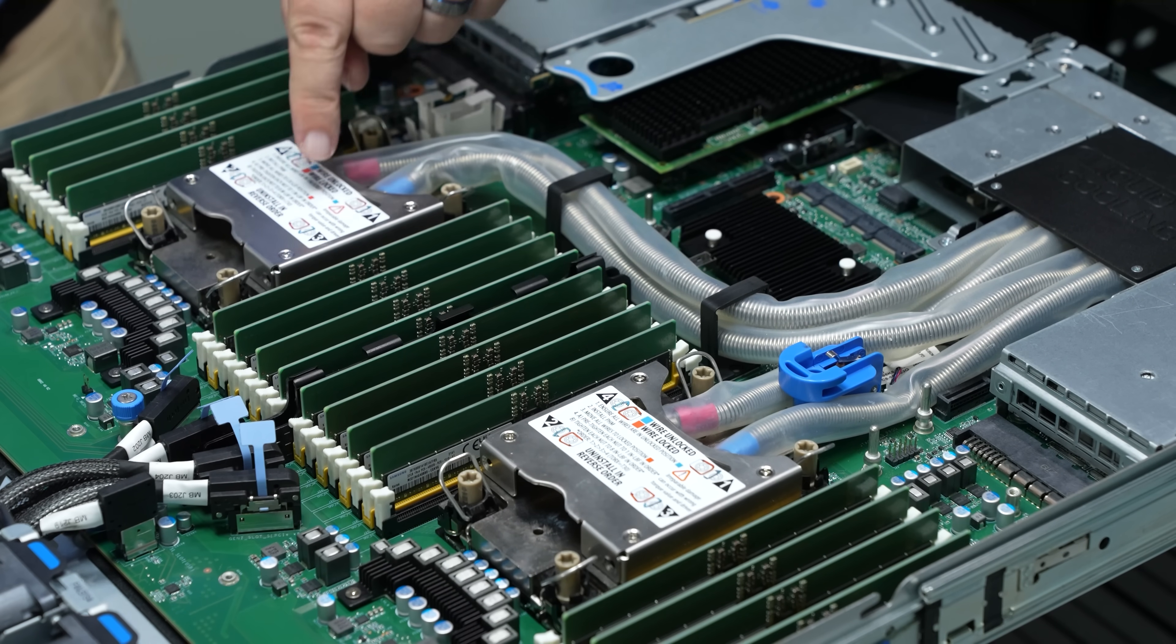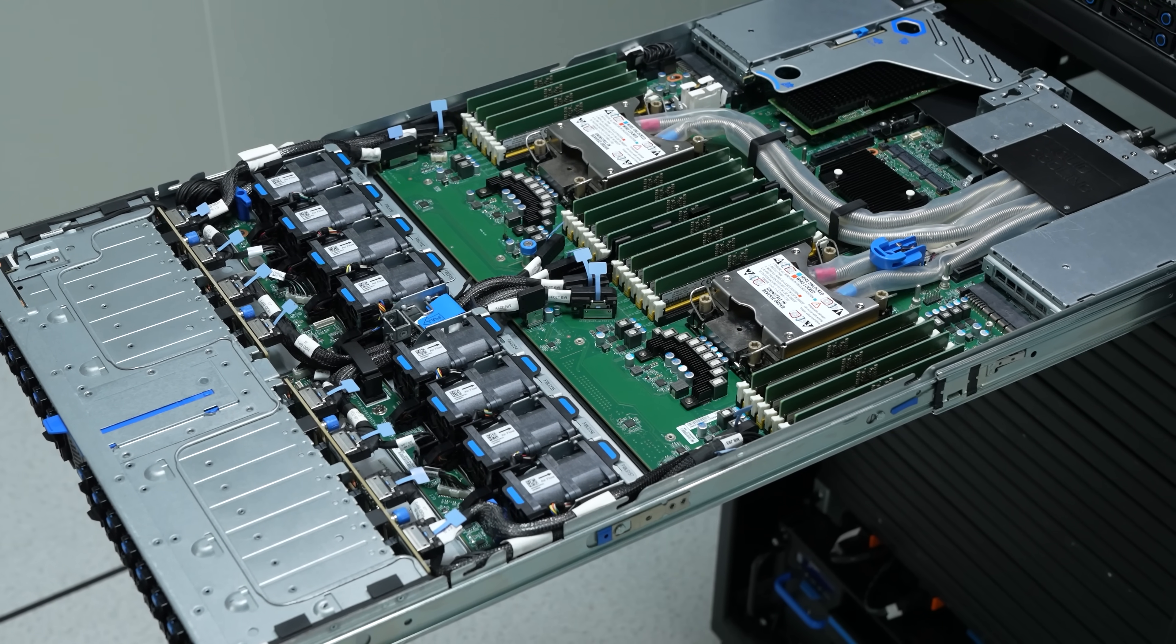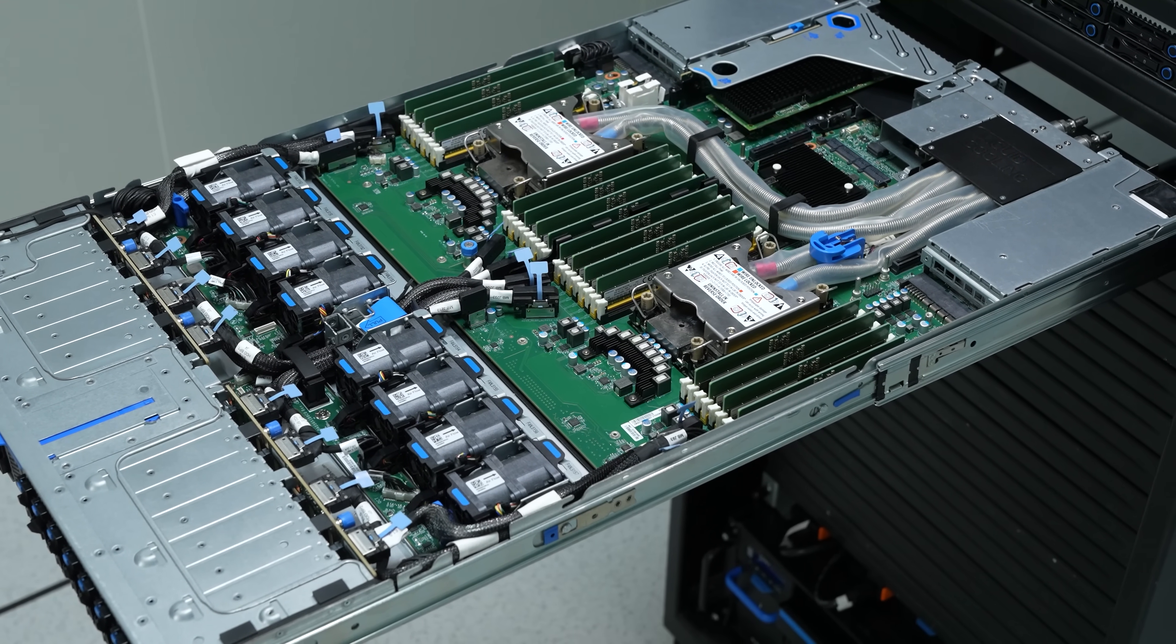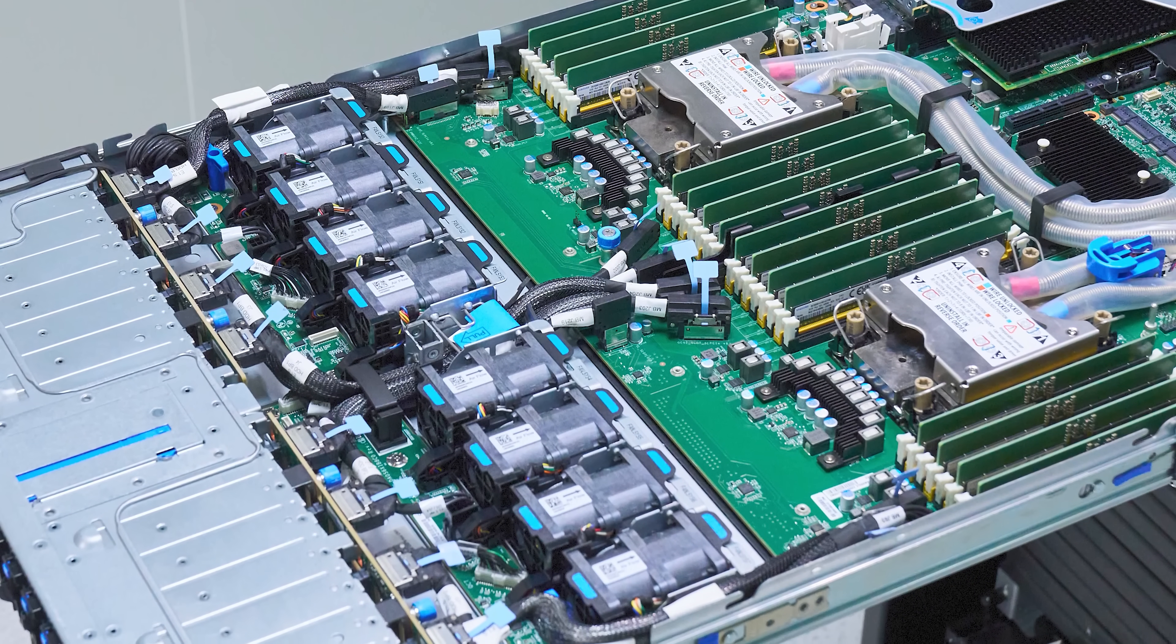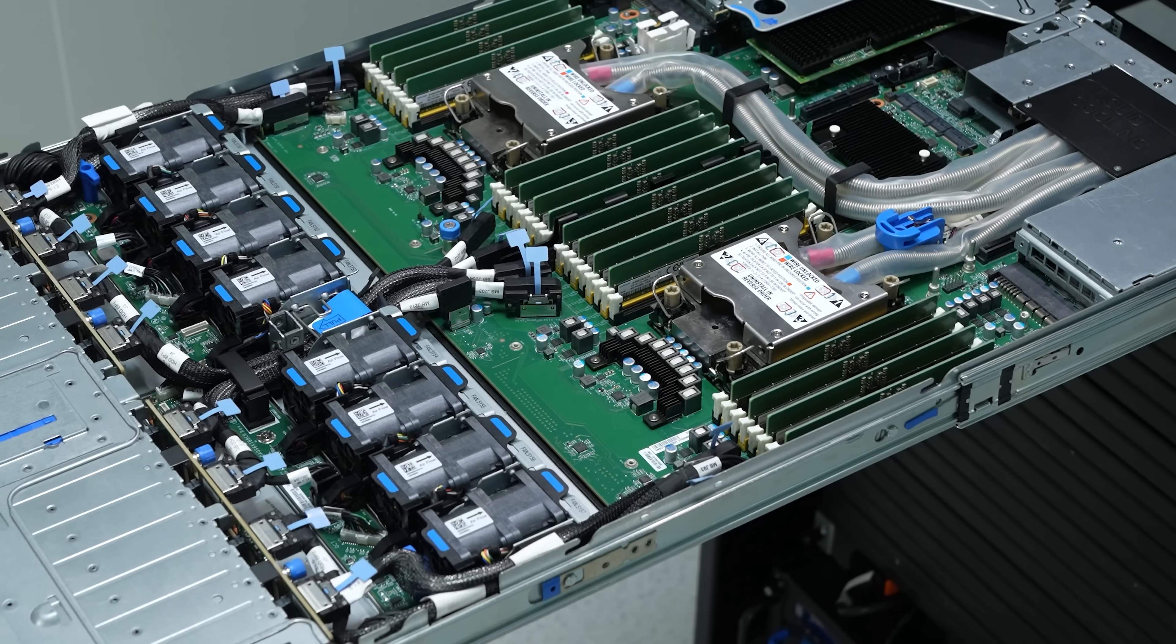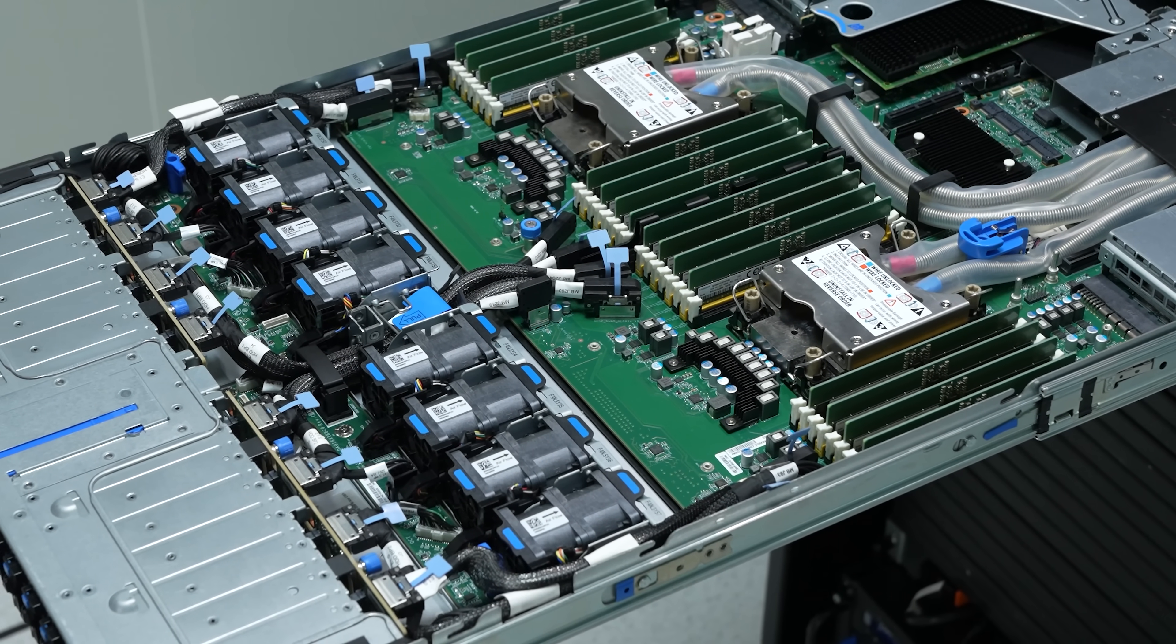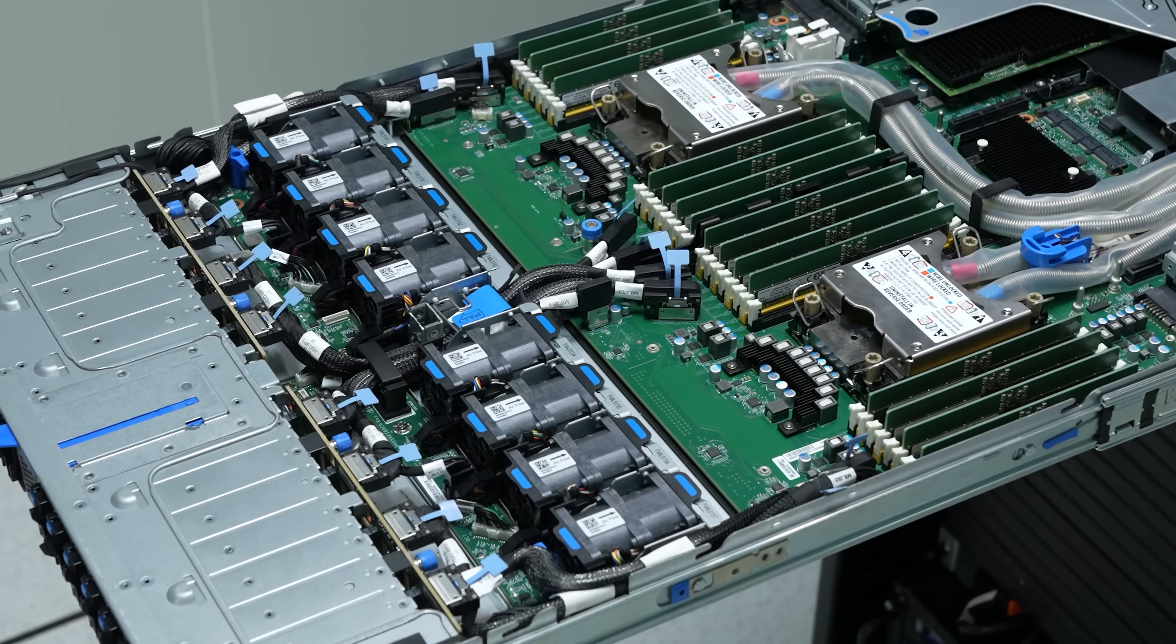Now, one point I just want to be very clear on is that there are different types of ways that you cool inside of servers. One of them is that you like liquid cool every single component. And if anybody has ever installed the like liquid cooling blocks for DDR5 or DDR4 memory, it is a total pain in the butt. So what a lot of folks do and a lot of companies do is that instead of that, they just cool the like really hot parts, the CPUs and maybe the GPUs with liquid cooling. And then they allow the chassis fans to cool things like the DIMMs as well as the add-in cards. Oh, and of course, storage as well. Now, what all that means is that we do have fans in the system. But the difference is that instead of running these things at like super high percentages where they're not that efficient, we can run them at much lower RPMs and therefore they use a lot less power.